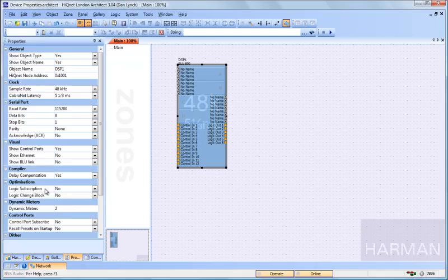Turning on logic subscription will limit subscriptions to only logic sources and logic ends, making London Architect ignore all the other devices. This won't affect logic processing, but it will cause London Architect to not subscribe to those objects, not display their indicators on the screen, and therefore not take up CPU time on the device. The logic change block, very much the same. It causes logic sources and logic ends only to be written to the change block, again freeing up some CPU cycles. Not something you generally have to worry about.